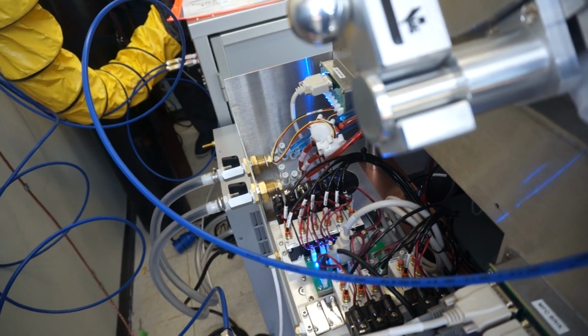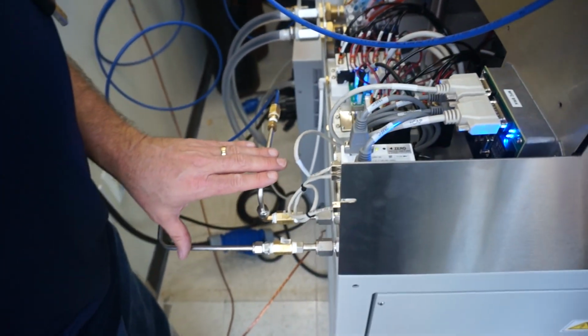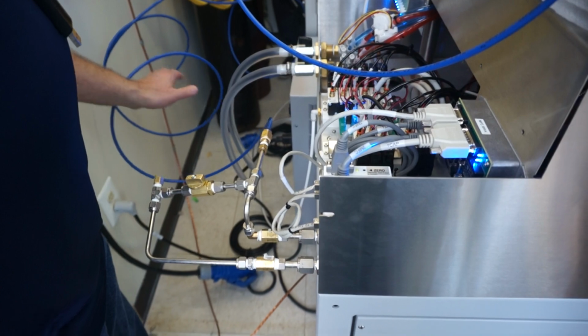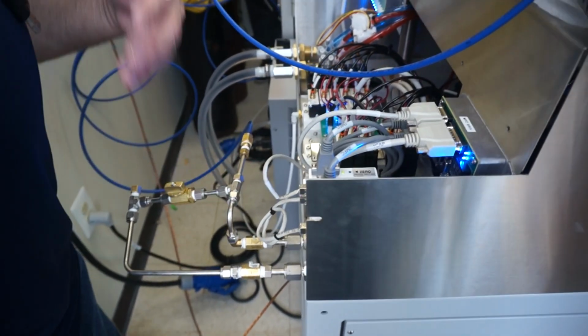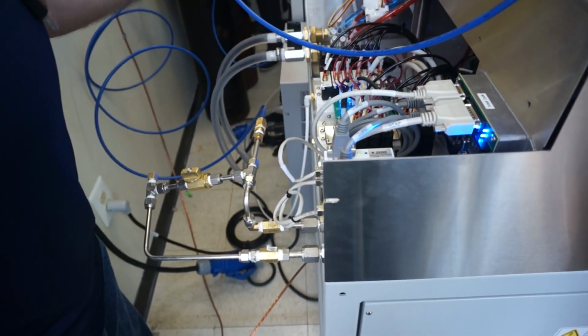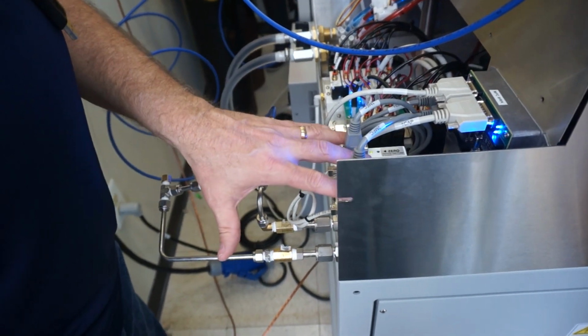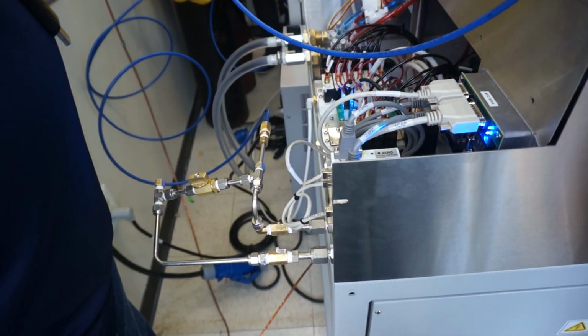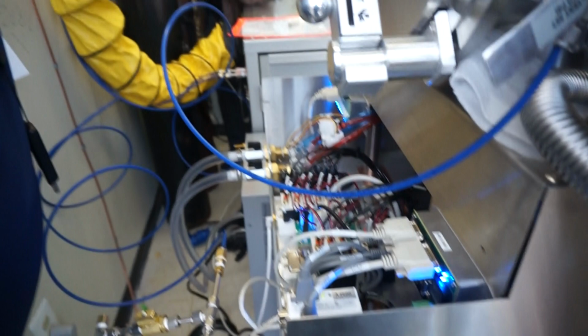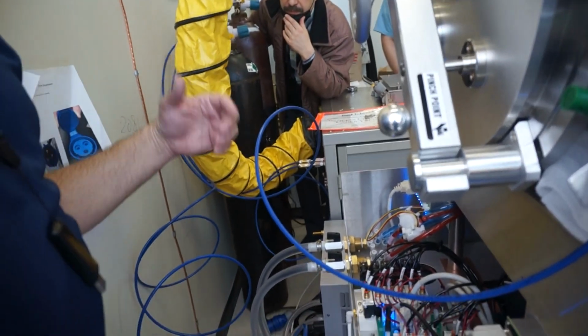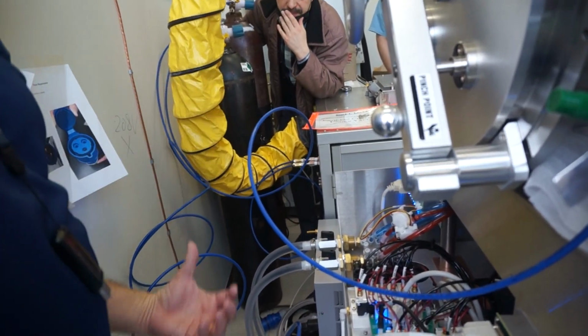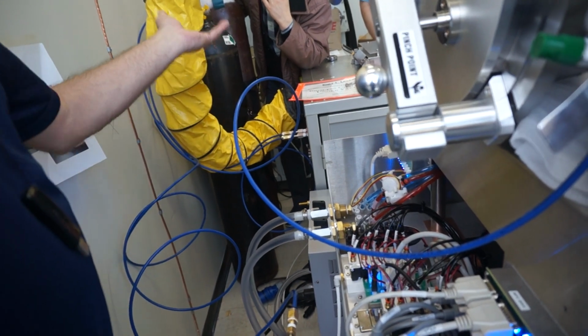And whenever I first powered this tool up, what I like to do, because this line's exposed to air, I go through the software and I systematically open up the valves and the mass flow controllers, and I pull a vacuum back to an isolation valve. I was not able to completely evacuate these lines, so we got to fix some leaks.